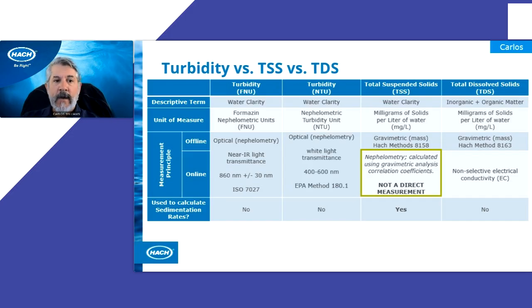If you look down at this third row, where we're looking at offline and online, under FNU, the FNU uses a light source at 860 nanometers, and that conforms to the ISO method for turbidity reporting, ISO 7027. In the second column, the NTU values conform to the EPA method 180.1. If you'll notice, the major difference is that there is infrared light, which is essentially colorblind, for the ISO method, and then we have light in the visible spectrum for the EPA method.